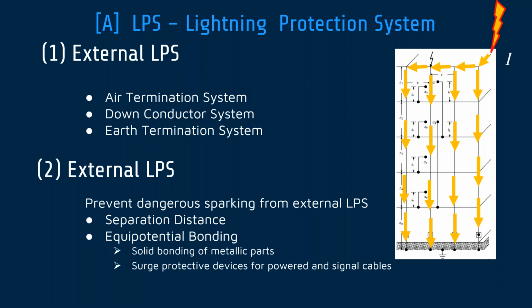The moment that current flowing down the tower through the resistance at the bottom increases to a point where it's almost reaching the BIL of the insulators on that line, before it gets to that value, we have a surge arrestor there that switches on. It shorts my 765 kV phase conductor to the tower. The tower is not sitting at 0 volts. The tower is sitting at some scary, much higher voltage, 2 point whatever megavolts it is, in order to reach the BIL value, but it is only 200 microseconds. So my surge arresters start operating as high-speed switches, better than any breaker can operate. So when we want to manage our lightning, maybe we should look at surge arresters doing the switching for us.